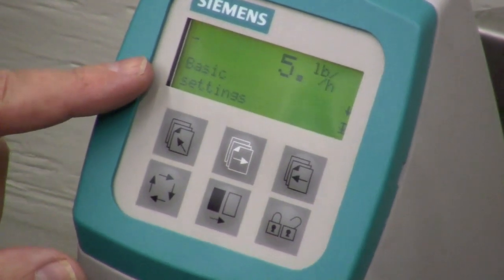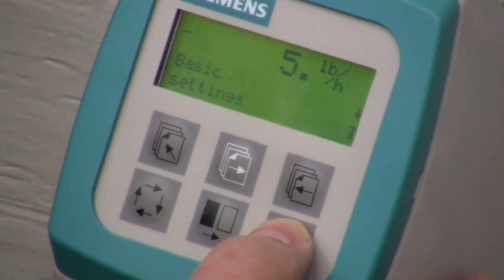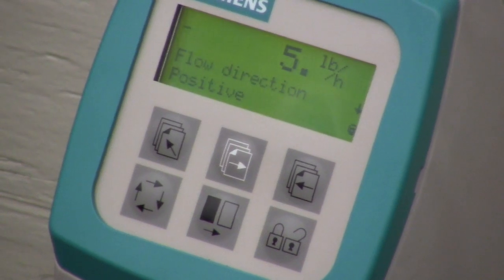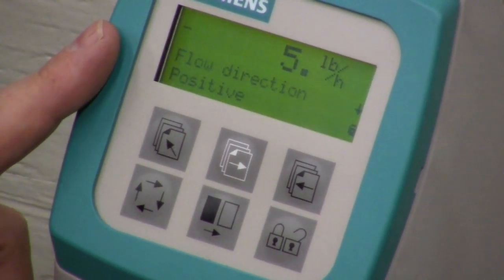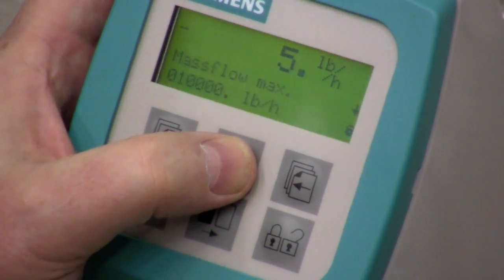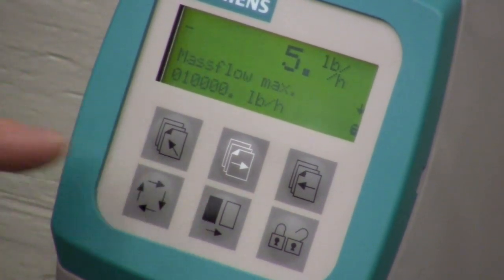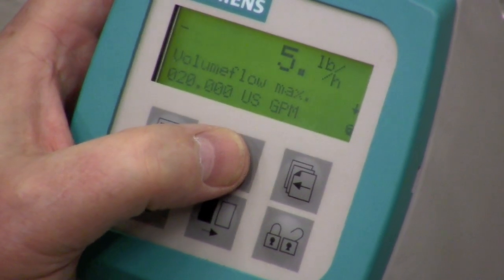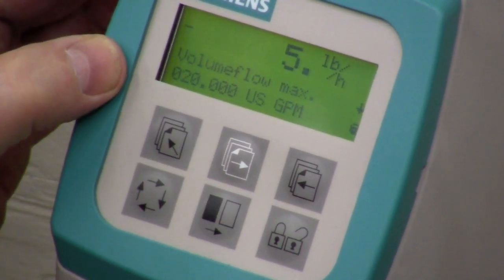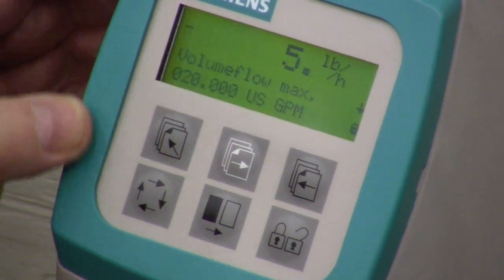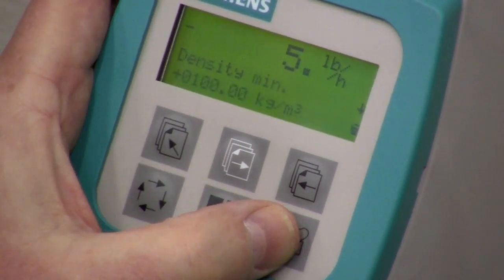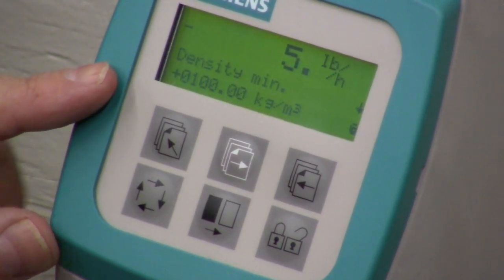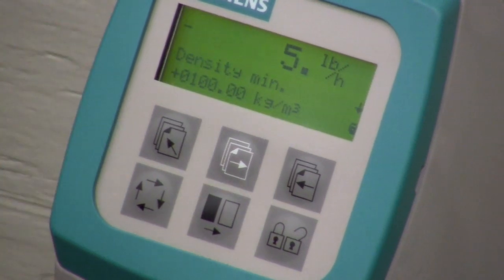The first thing that comes up is basic settings. We hit the unlock key and this is where we start selecting our basic setup for the device. Flow direction — which way is positive, which way is negative. You can also set your maximum mass flow; we have it set up for 10,000 pounds per hour. Then you have your volume flow max — currently set for 20 US gallons per minute. And density — if we unlock here, we can change our density depending on what you're going to be measuring.